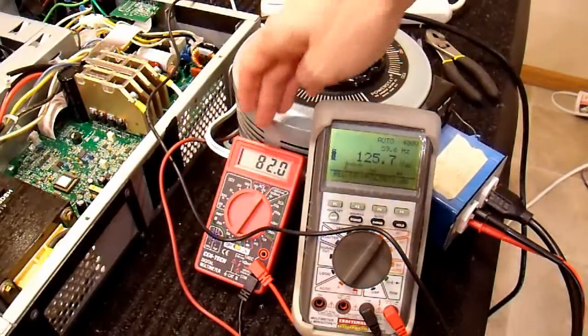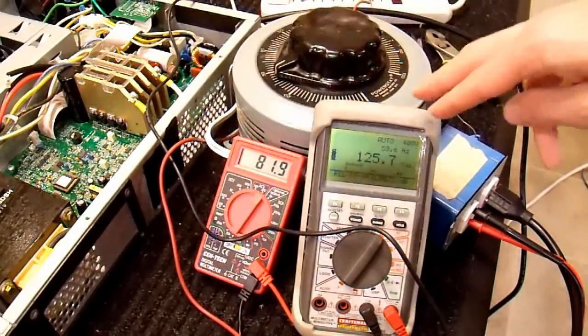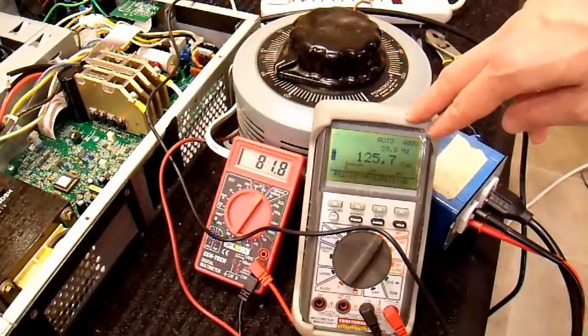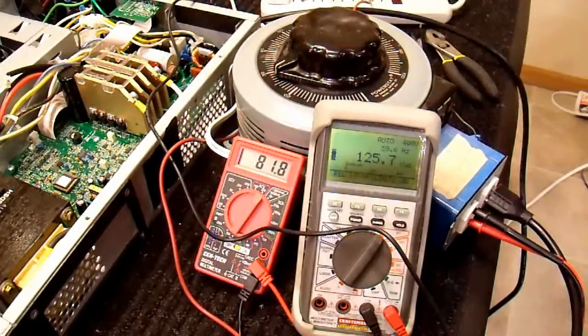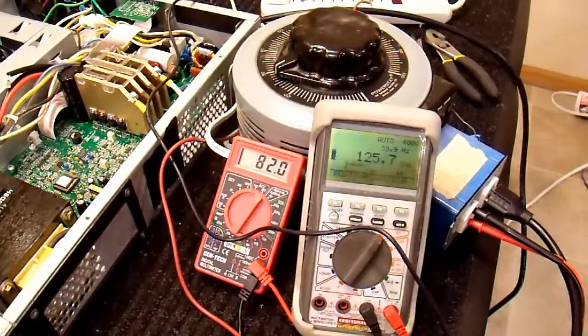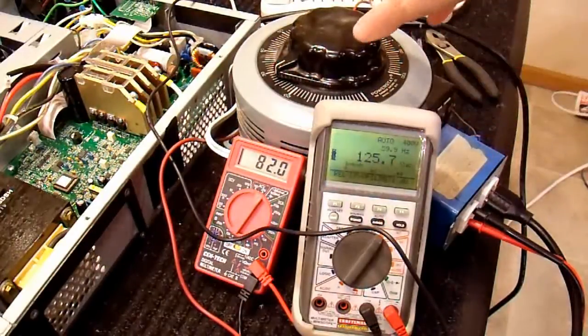So at this point, my input voltage is 82 volts. And you can see that the voltage between one phase of the wall and the output of the UPS is nice and stable. It's still at about 125 volts.